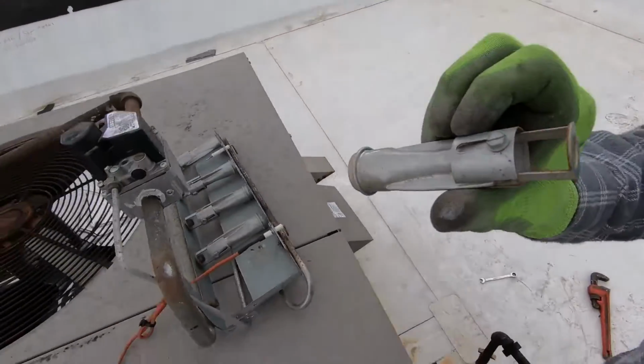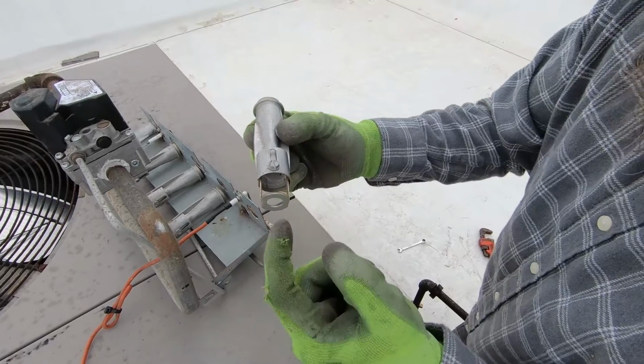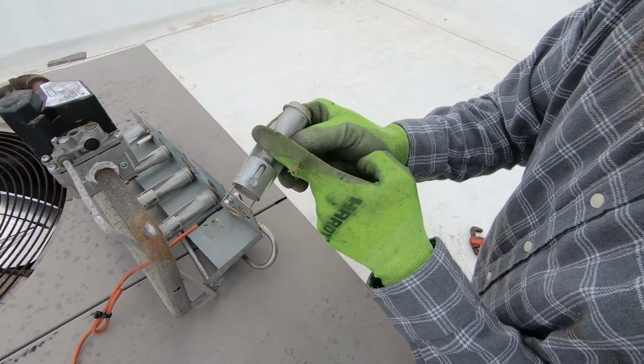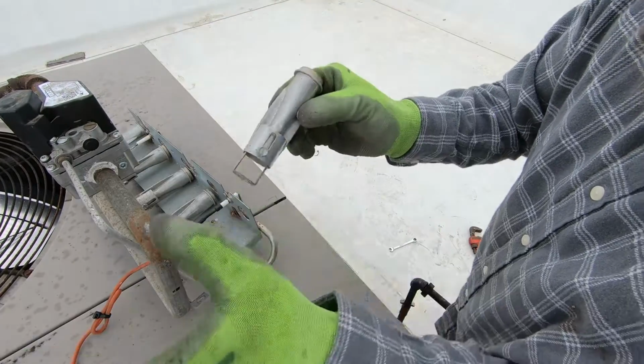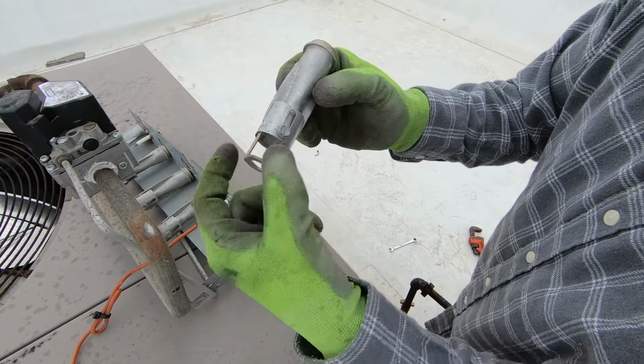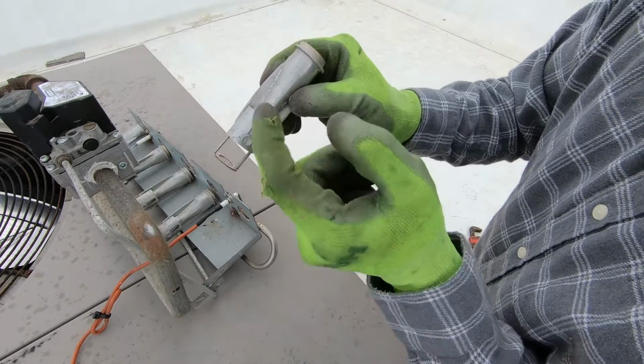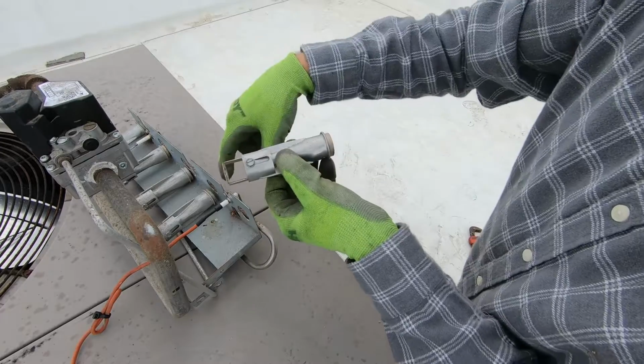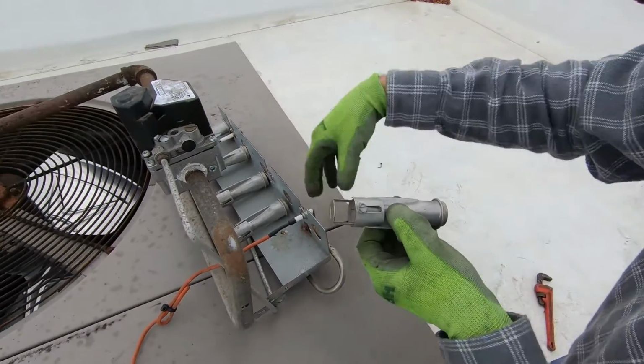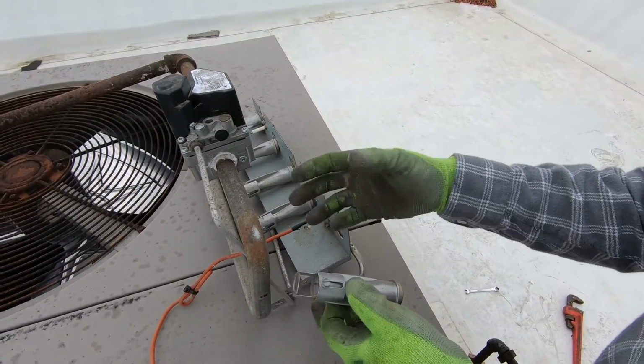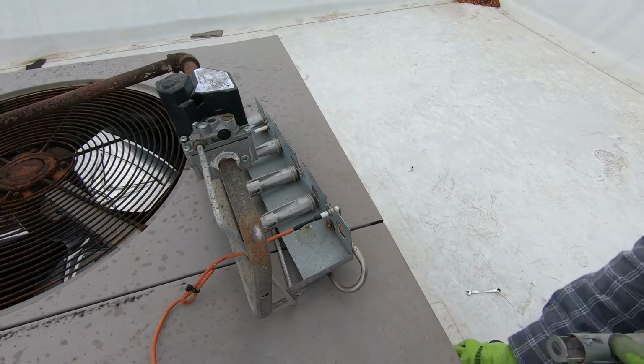So that's what's happening. The gas was being delivered into the burner, but it was only coming to here, and it was all spewing back out where the air mixture, where the air enters to mix with the gas. It was coming back out, and then the other burners were lighting that gas that was accumulating in the burner box.